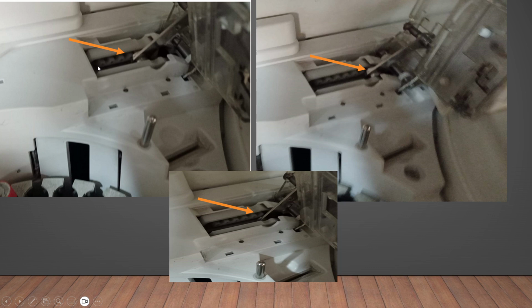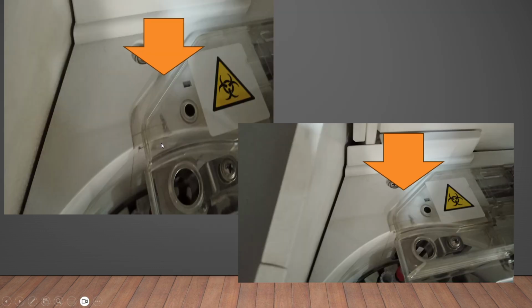So every time you lift it up, when you are closing, you have to open it completely to the top and then close it. This is one important thing, and every time you have to make sure that it fits properly. Otherwise the probe can actually touch the surrounding area, and because of that the probe may stop, or it may take air and give it as a sample clot or something like this.